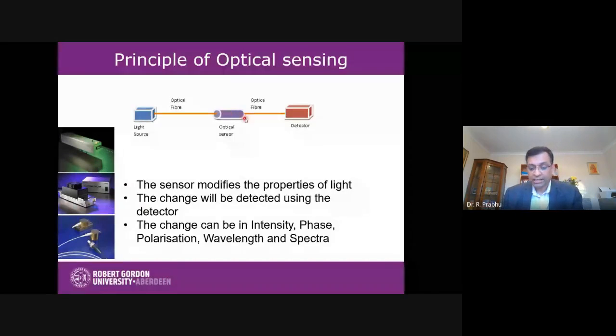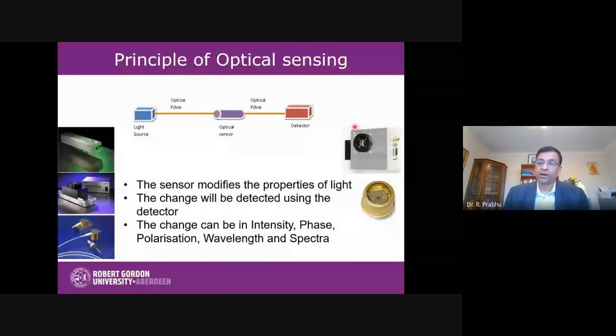On the other side, we have a set of detectors. These are photomultiplier tubes, which are expensive but highly sensitive. On the other side, we have cheaper sensors called silicon photodiodes, which are quite cheap compared to photomultiplier tubes but might be slightly lower in sensitivity. And now we have CCD-based sensors as well.